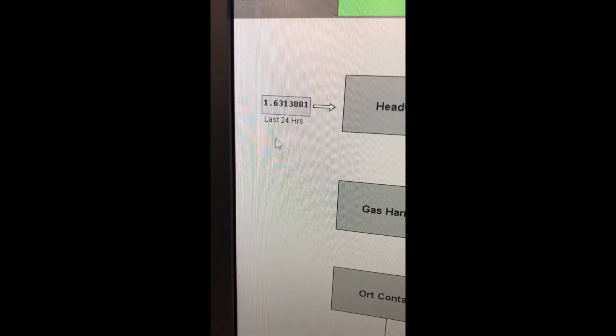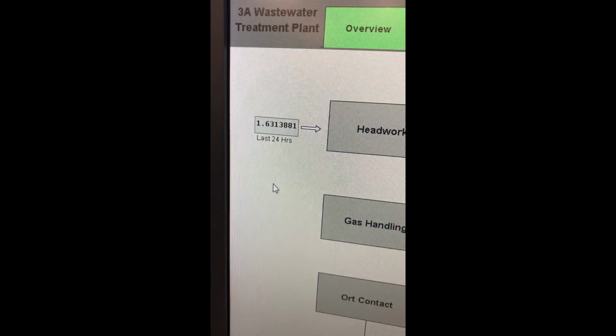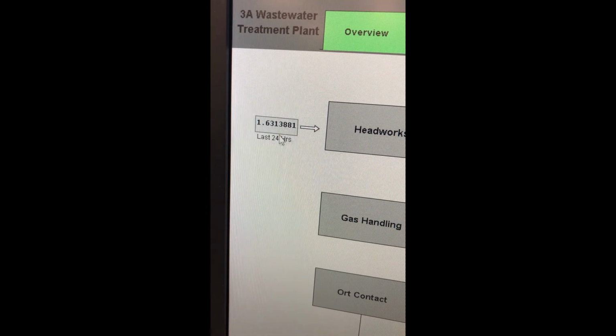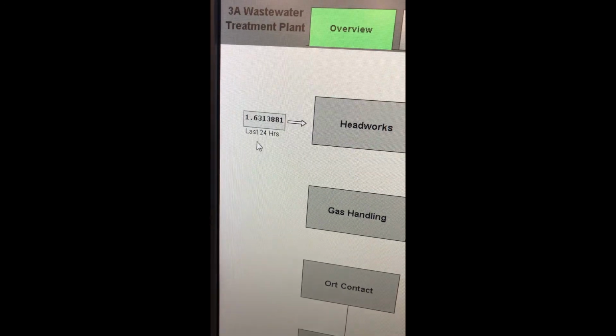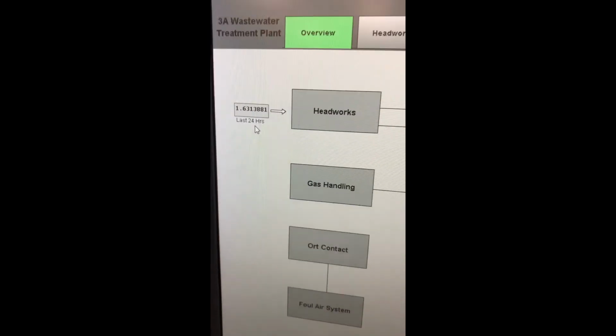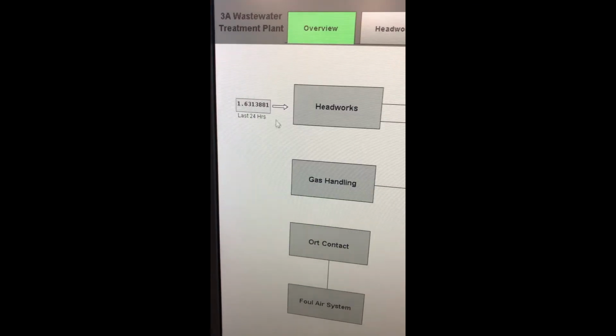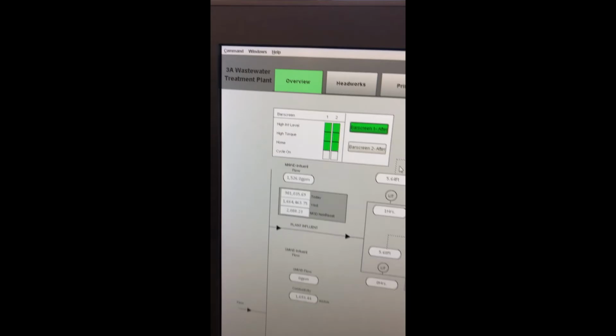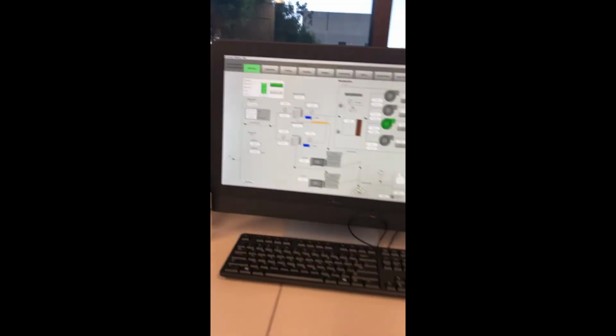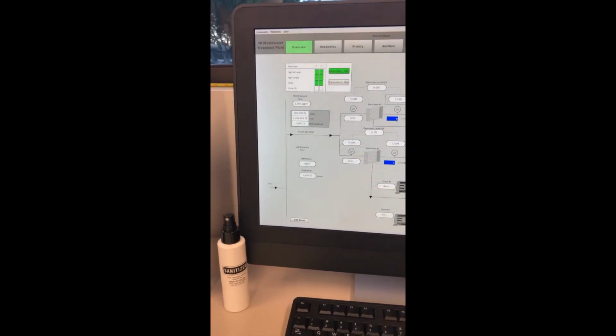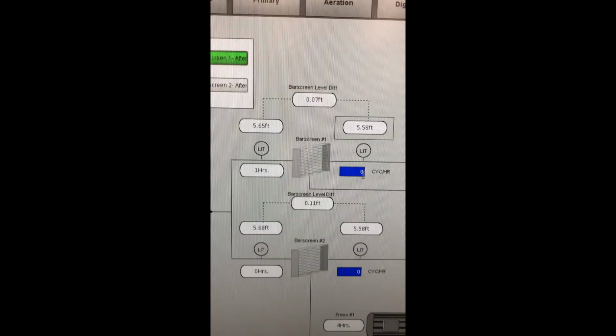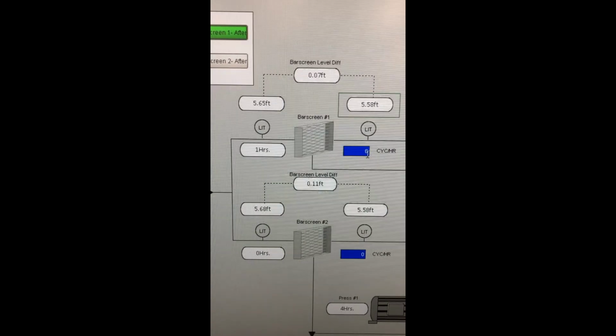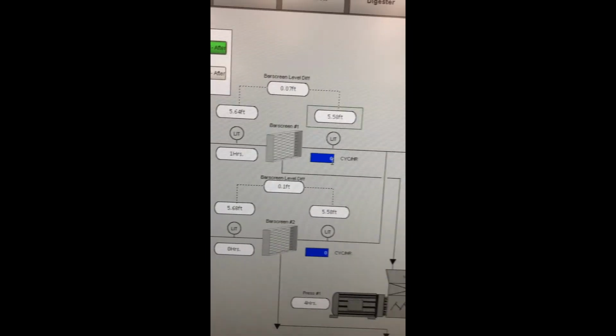You can see I've got a box here where I've got a quick glance look at the last 24 hours and how much flow has come to the plant. So that's 1.631 MGD. Then we can go to the headworks, and we can kind of back off a little bit here, and we can see what's going on where the sewage is coming into the plant. We've got our current flow coming into the plant. We've got the levels for the two bar screens that we looked at earlier, upstream and downstream, and the differential.